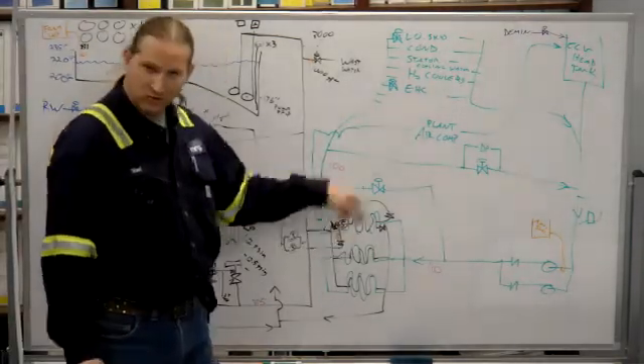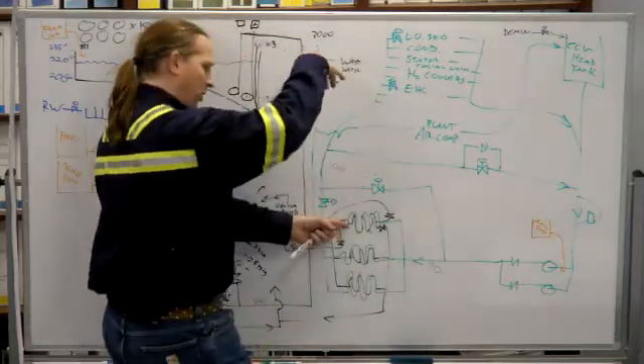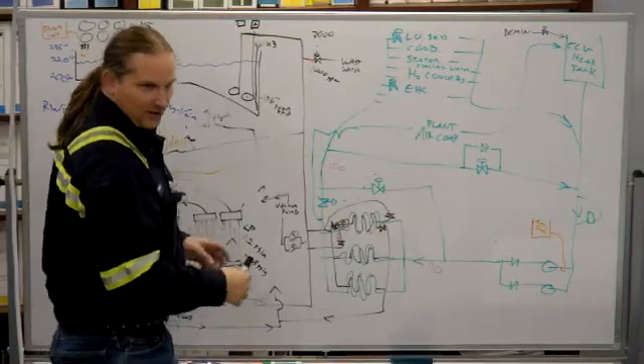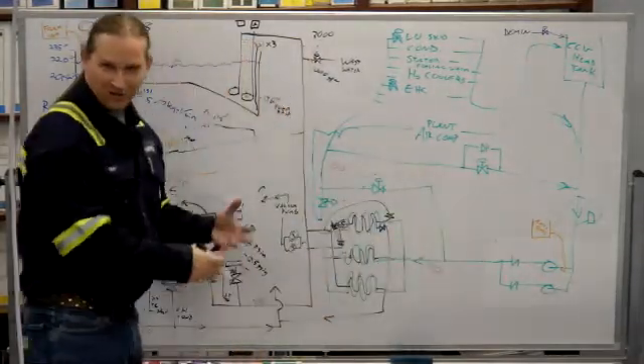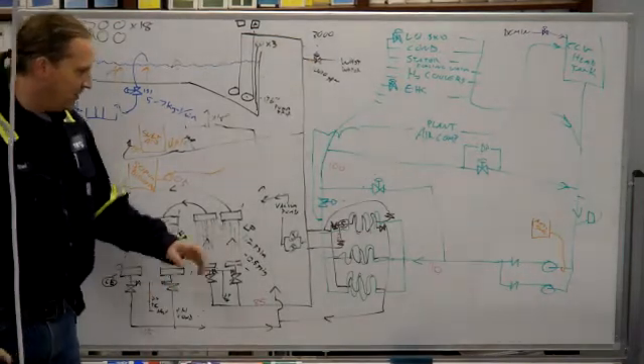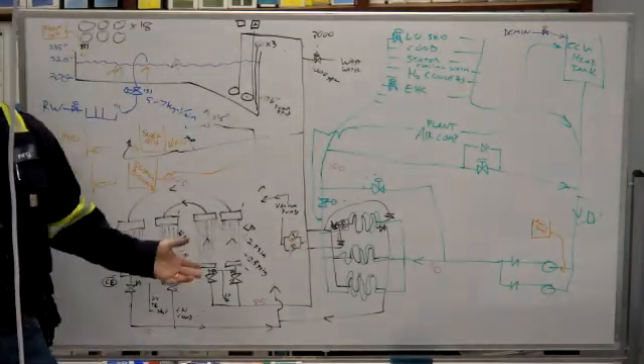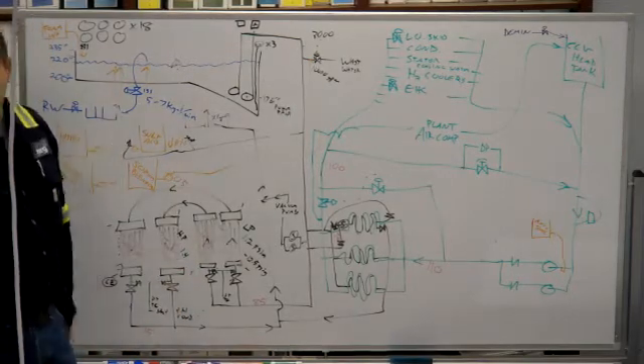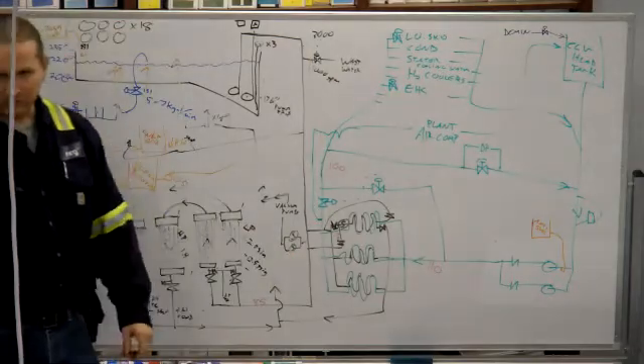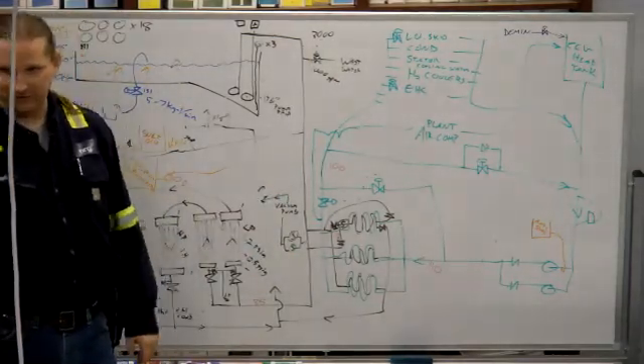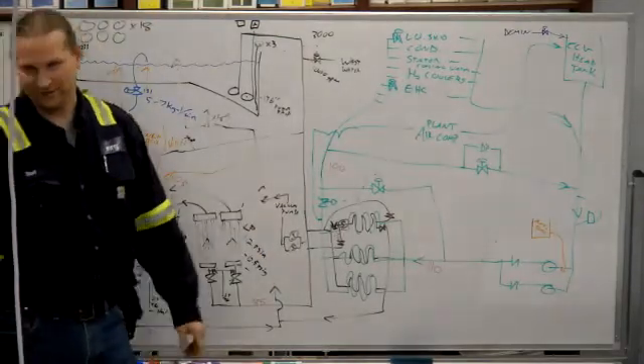So I draw this like it's a swirly line. What it really is, is a whole bunch of plates. And I want to say that circ water flows up across the plates and that cooling water flows down across the plates. And then on the circ water side, you've got that header has like a witch's hat type strainer that goes in there that catches all the mud and crap. Doing the strainer every week, you can see what you're doing in there. And you know you're not doing much. But coming out of an outage, when we built scaffolding in the damn cooling tower, then you're going to be doing this strainer three times a shift for the first day and a half. When we first start trying to pull vacuum, we're not getting any. It's too hot. And then that's why.